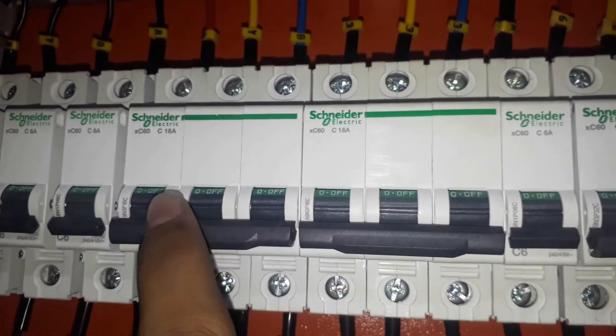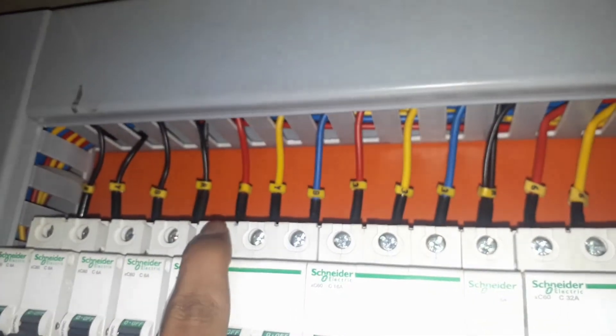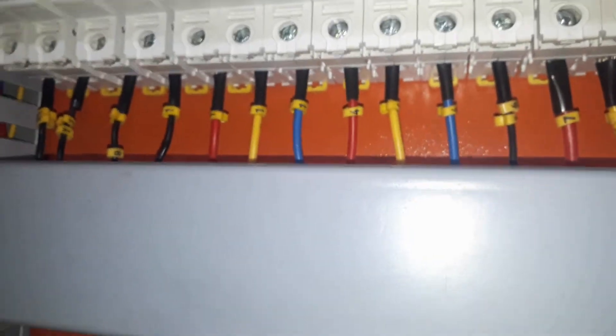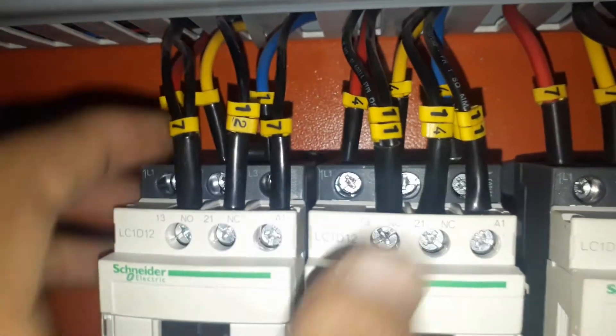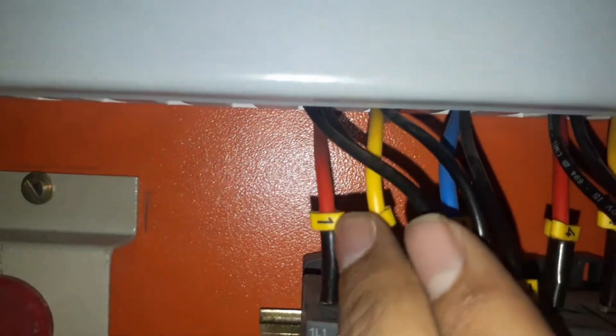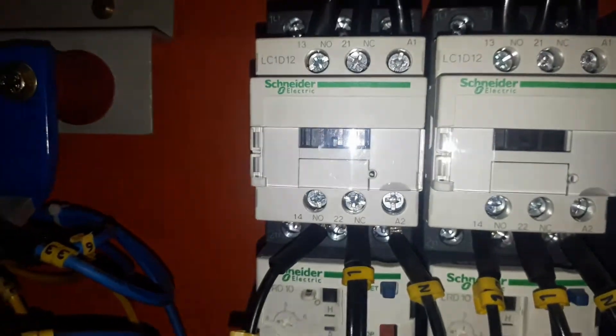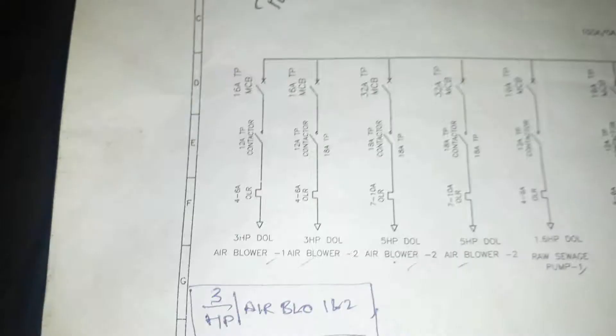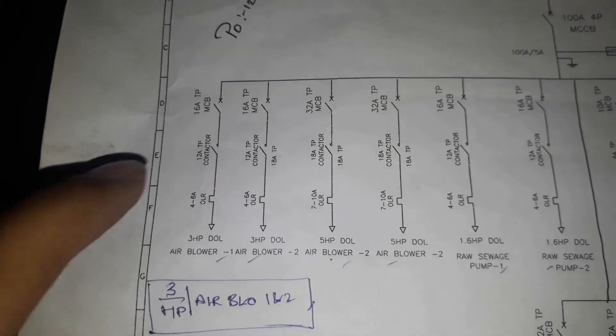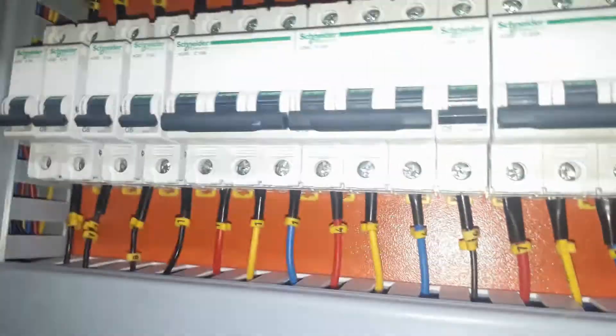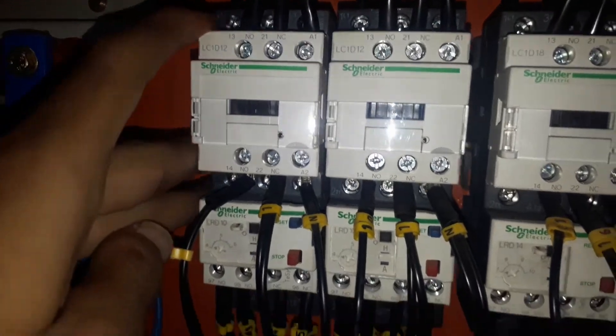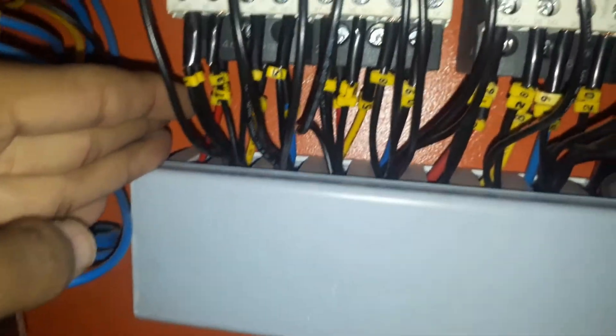After the CTs we have 13 pairs of DOL starters. On the first pair we have a 16-ampere three-pole MCB. Three phases R, Y, B are connected to this MCB and taken out from it, then connected to the contactor — a Schneider contactor. The R, Y, B phases from the circuit breaker connect to the contactor at L1, L2, L3. This contactor is a 12-ampere three-pole unit. From the contactor the output goes to the OLR, which is rated 4 to 6 amperes.